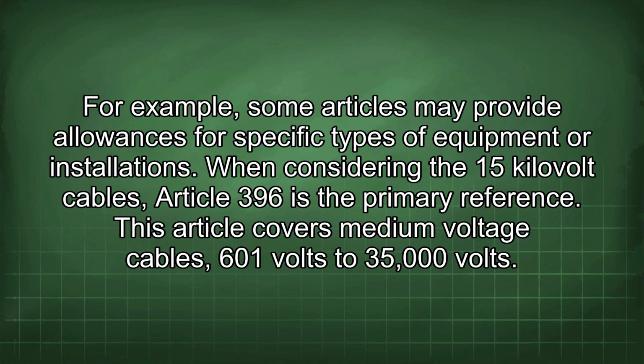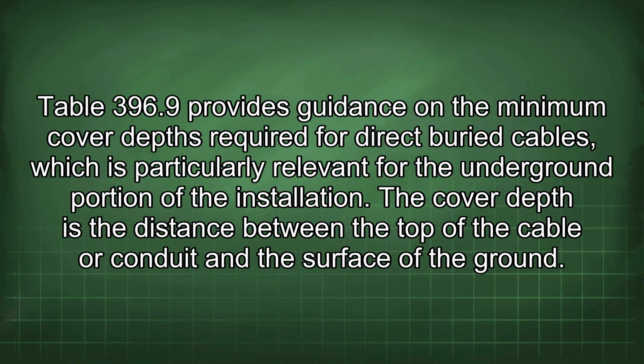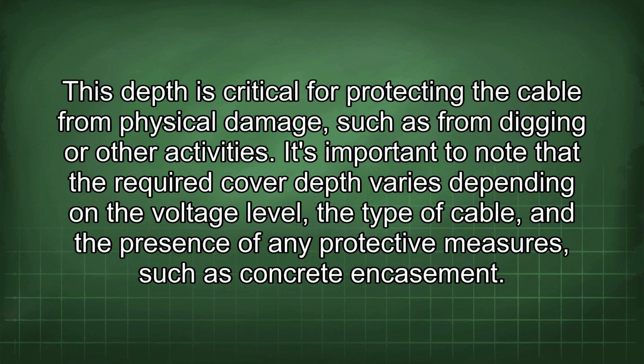When considering the 15 kV cables, Article 396 is the primary reference. This article covers medium voltage cables 601 volts to 35,000 volts. Table 396.9 provides guidance on the minimum cover depths required for direct buried cables, which is particularly relevant for the underground portion of the installation. The cover depth is the distance between the top of the cable or conduit and the surface of the ground. This depth is critical for protecting the cable from physical damage, such as from digging or other activities. It's important to note that the required cover depth varies depending on the voltage level, the type of cable, and the presence of any protective measures such as concrete encasement.